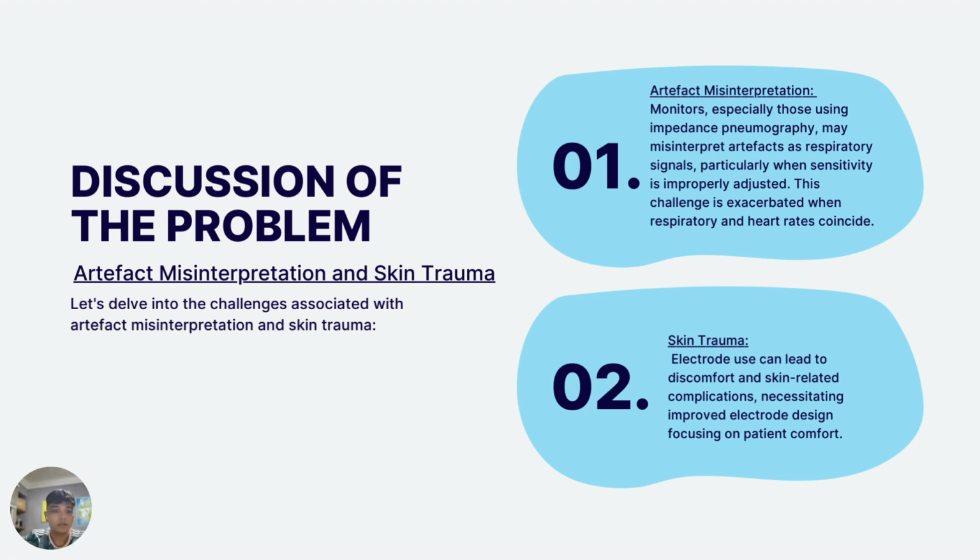Furthermore, artifact detection requires the implementation of advanced algorithms for artifact recognition and rejection. These algorithms can enhance the accuracy of apnea detection by distinguishing between genuine respiratory signals and artifacts. Manufacturers should prioritize refining sensitivity controls, particularly for monitors utilizing impedance pneumography.